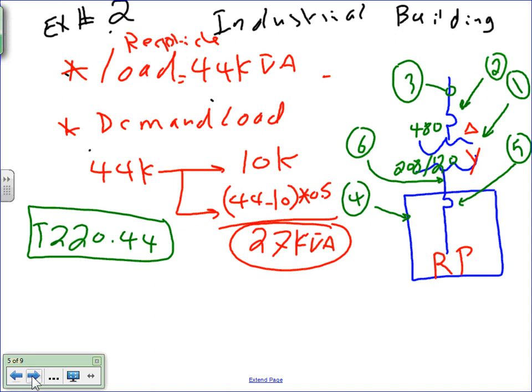So I need to size the following. Number 1, the transformer. Number 2, the overcurrent protection device on the primary. Number 3, the feeder on the primary of the transformer. Number 4, the panel on the secondary. Number 5, the overcurrent protection device for the panel. And number 6, the conductor that goes into that panel. This is a typical transformer receptacle panel. Every building you get into, guys, you're going to have this type of scenario: a transformer that feeds the receptacle panel. Why? Because we run our receptacles in the US at 208. So you have to have transformers.